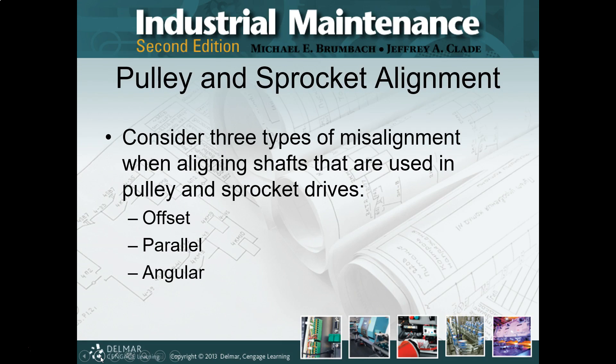Just like before in the pulleys and sheaves — the first mechanical power transmission in Unit 6 — a straight edge is the best way to go. If everything's flush and everything has an equal measurement, you're parallel. And you don't have an offset. You may still have an angular, but at least you know you are good to go on offset and parallel.